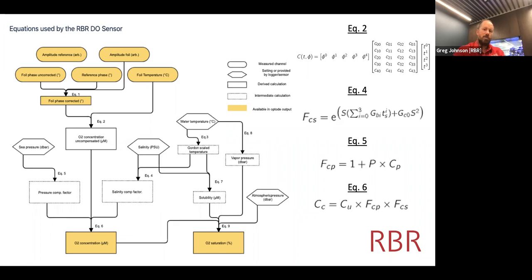We correct the foil phase with the reference, which gets rid of most of the aging effects. And we have the foil temperature. And those are all available as outputs. But what you're really typically interested in is the oxygen concentration in the bottom left, or if you prefer it in saturation terms in the bottom right. The salinity compensation and pressure compensation can also be applied.